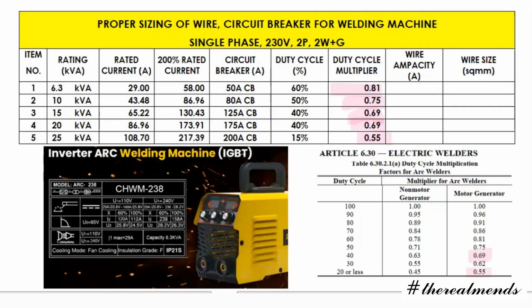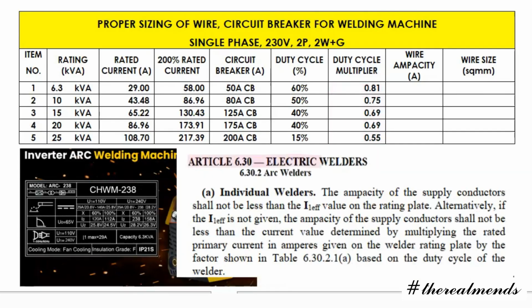Okay, so that's it. And then we have a reference PEC code for the wire ampacity, from Article 6.30, electric welders. So for these individual welders, the ampacity of the supply conductors, known as the wire, shall not be less than the I effective of the rating plate. So if you look on our nameplate, we don't see an I effective, but we have an I max. Okay, so there is no I effective.